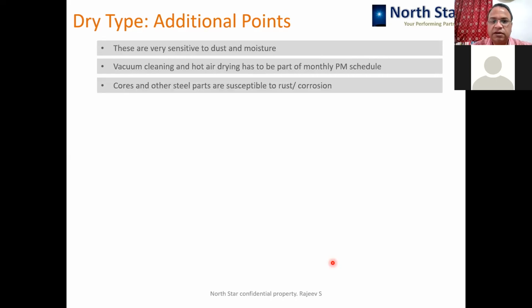Okay, then all these cores and steel parts are exposed to the environment. They are not in the oil, so they are not protected from moisture or rust. So they are more likely to get rusted, especially the core, which is a magnetic steel and an active component of the transformer, that gets rusted if not protected by a proper anti-corrosive or anti-rust coat on the core. So that is to be seen.